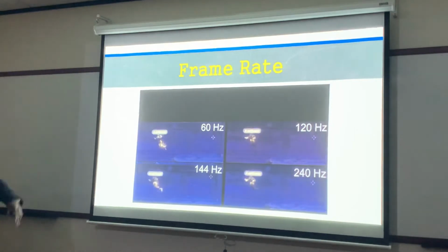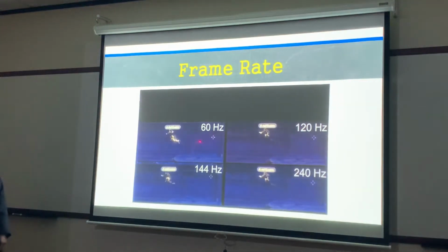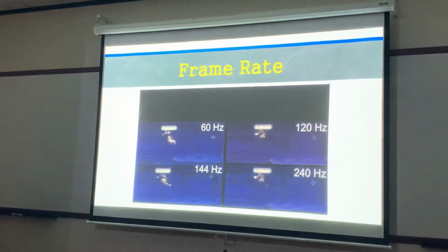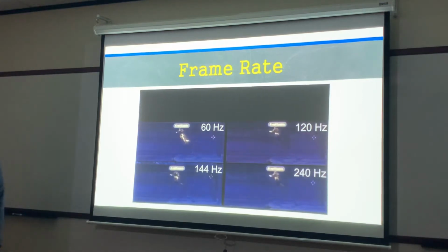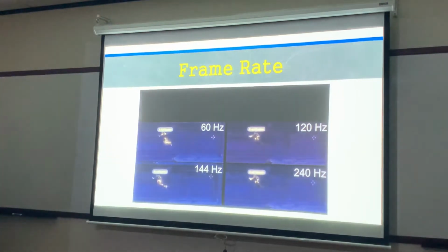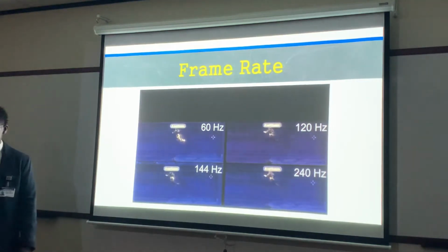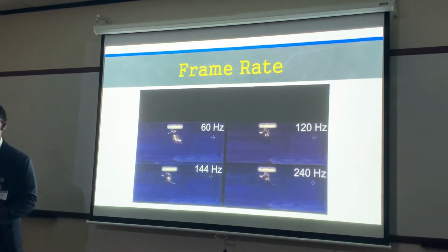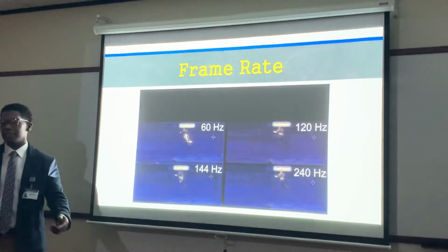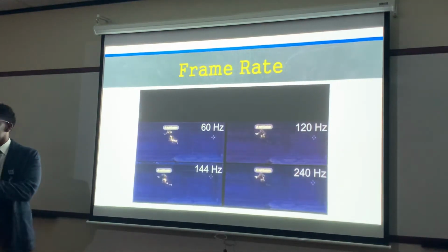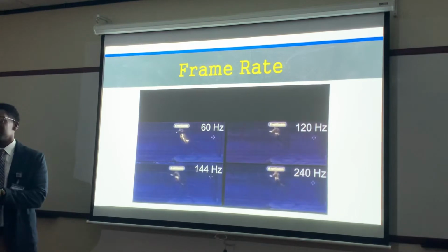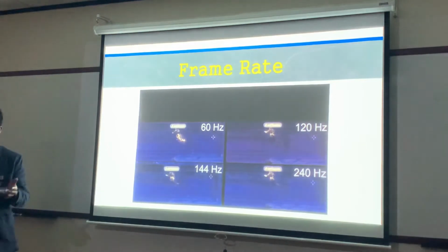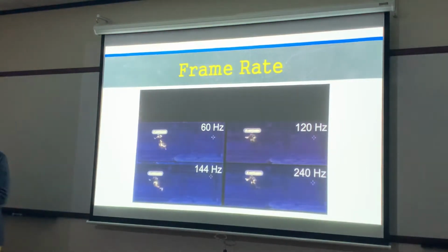Okay, but I like this image right here to explain low frame rates versus high frame rates. With high frame rates, it looks like it's moving in real time, like our ultrasound system. Remember I said the more applications you put on your ultrasound system, the slower it moves. When you have pulse wave Doppler and color Doppler on at the same time on top of a 2D image, your frame rate slows down tremendously. And sometimes you can even see that the images aren't being acquired as fast. To the naked eye, sometimes we can't tell because sound is still moving faster than we can see.